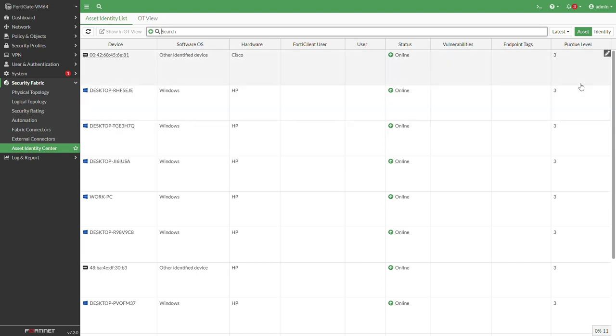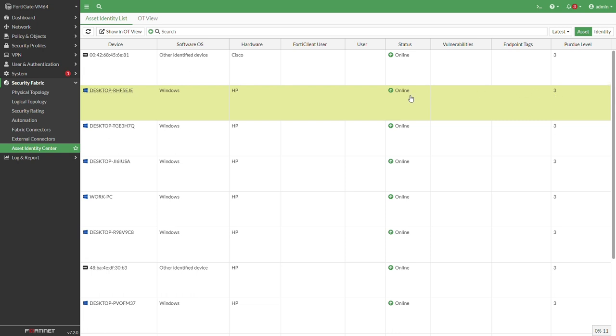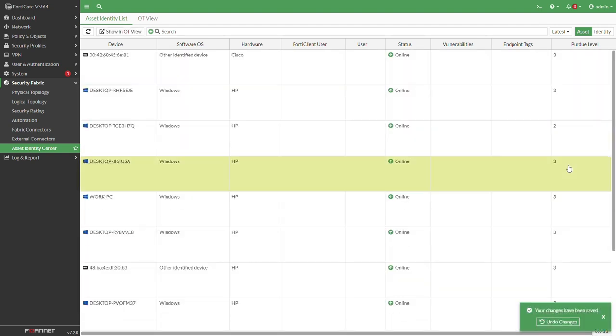I'll just assign the devices, the PLCs, the HMI, the historian, the engineering station to their different Purdue level. You have an edit icon next to the different levels. By default the FortiGate is in level 2. Now play around, just assign level 1 to the different PLCs, level 2 or level 3 in some cases to the historian, to the engineering station and so on.